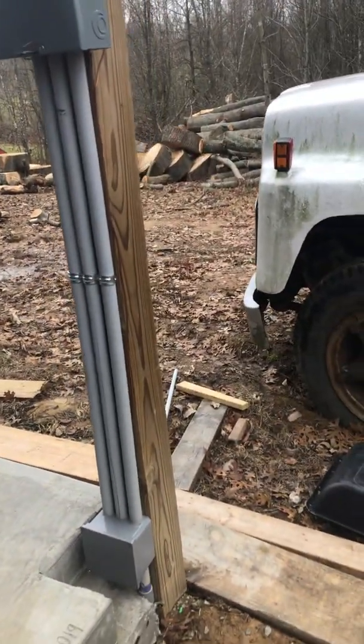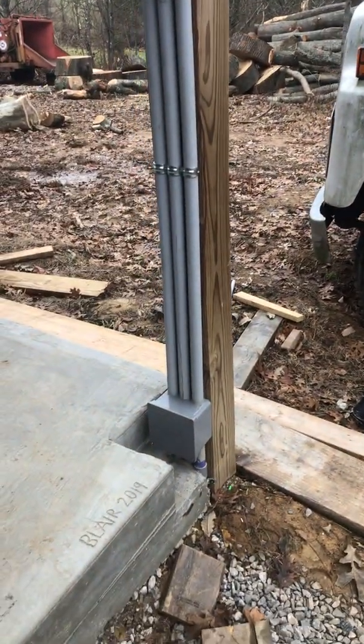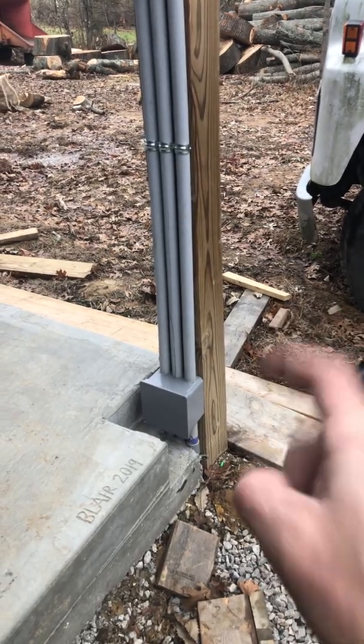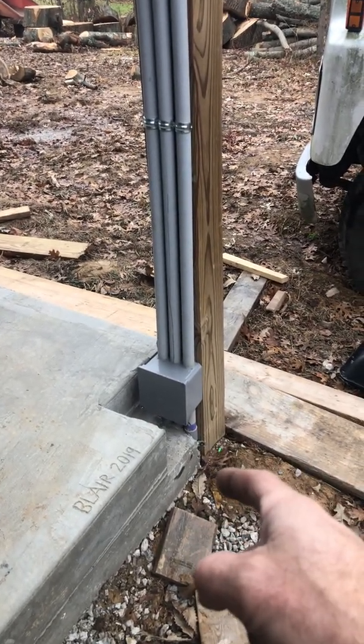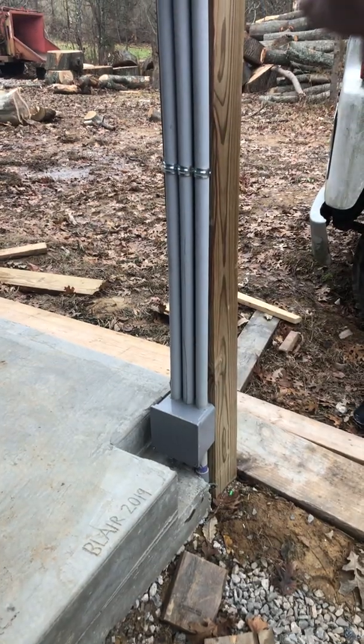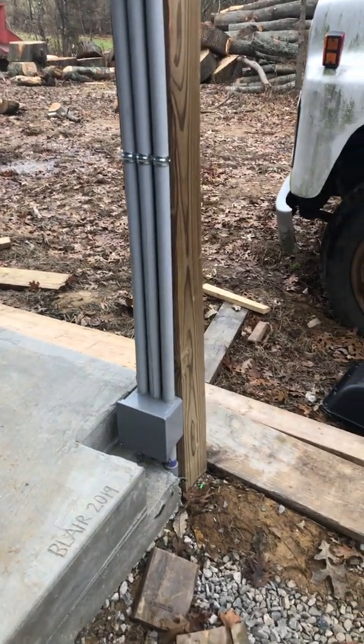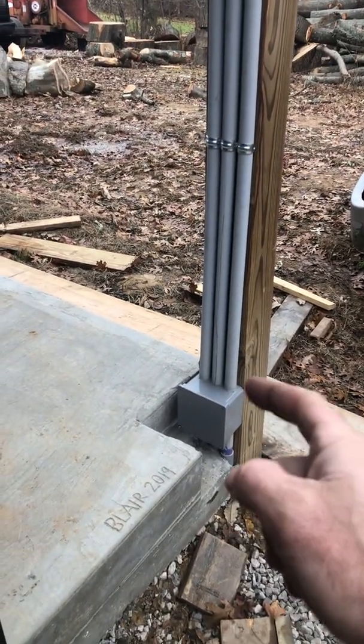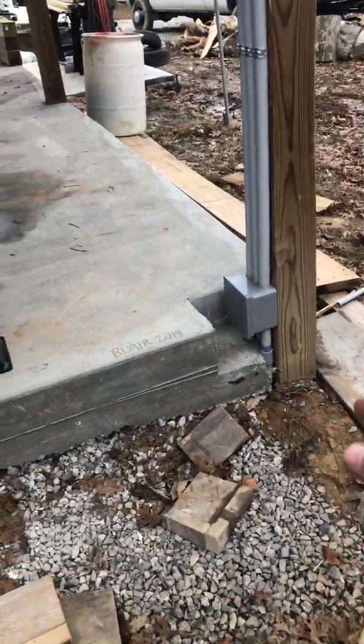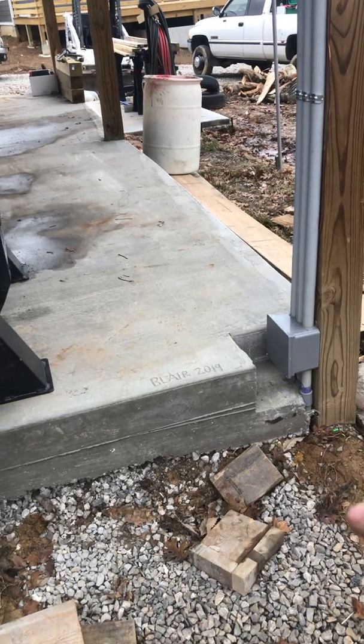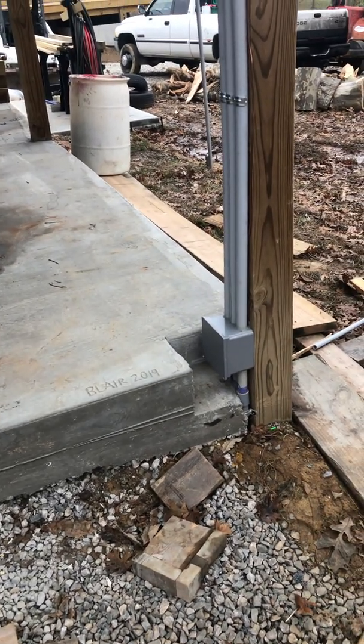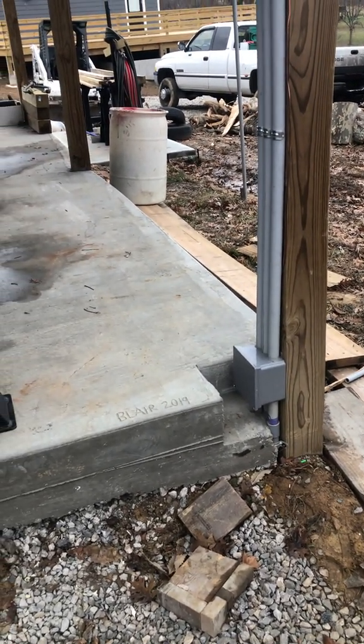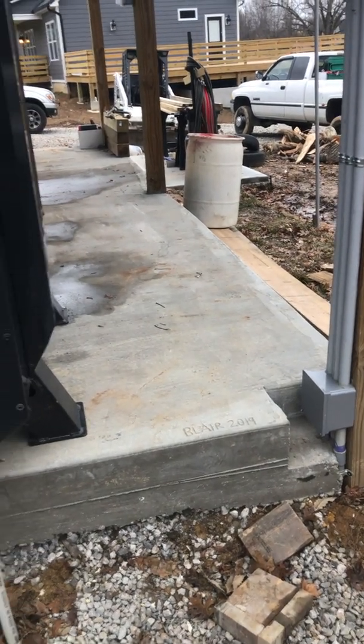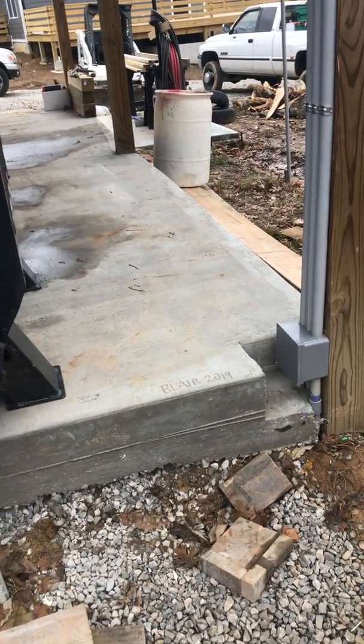Hopefully, if you guys plan on doing this, you can avoid a couple of the mistakes I made. My 1 inch conduit comes up right here, and I'll put in a sub panel. The reason I have this junction box and my concrete cut out is I decided to run 6/3 wire out here so I could have 60 amps and power other things rather than just this pump.